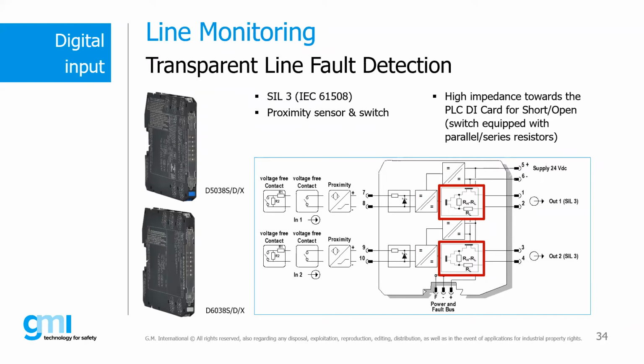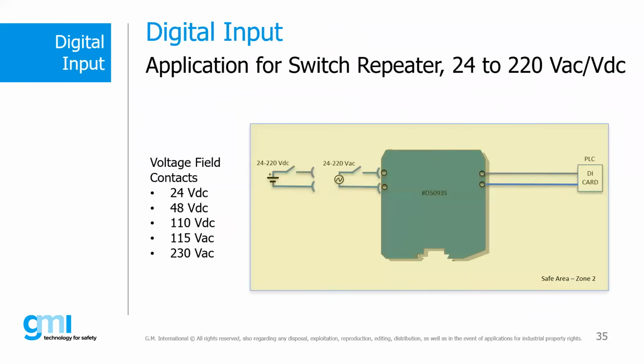Let's see now some particular application involving digital input isolators. The typical application is where we have to isolate a voltage-free contact or an Namur sensor in the field. And in this case, we use the classic digital input barrier or an isolator.